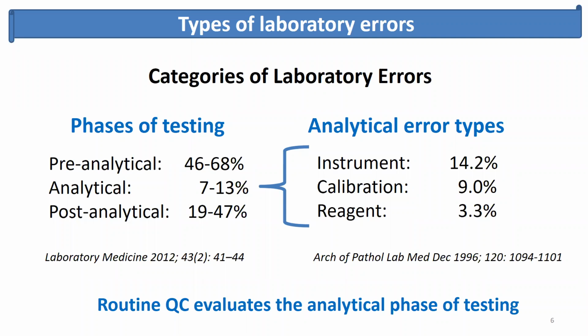Another study that examined more than 670,000 proficiency testing survey submissions from 665 laboratories found that PT failures due to analytical errors consisted most frequently of instrument errors, like the instrument needed maintenance, or maybe the instrument had a pipetting malfunction, followed by calibration errors. For example, the assay was miscalibrated or calibrators were prepared improperly, and then reagent errors, such as reduced stability of an onboard reagent.